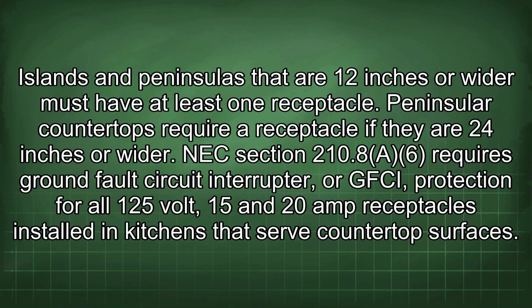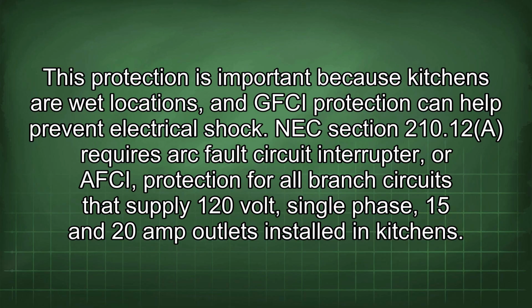NEC section 210.8(A)(6) requires ground fault circuit interrupter, or GFCI, protection for all 125 volt, 15 and 20 amp receptacles installed in kitchens that serve countertop surfaces. This protection is important because kitchens are wet locations, and GFCI protection can help prevent electrical shock.